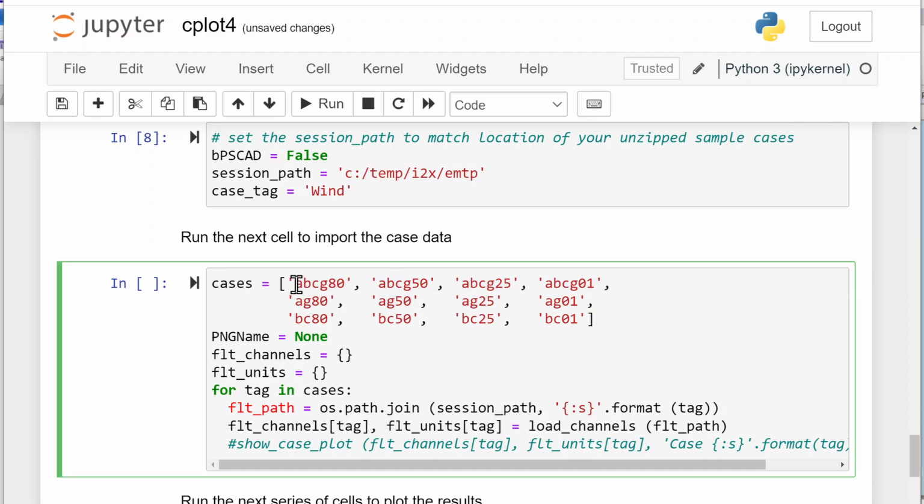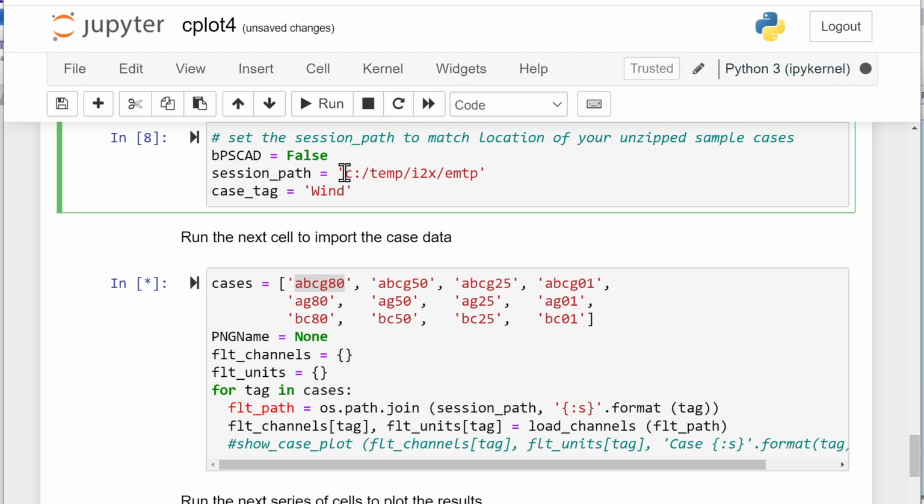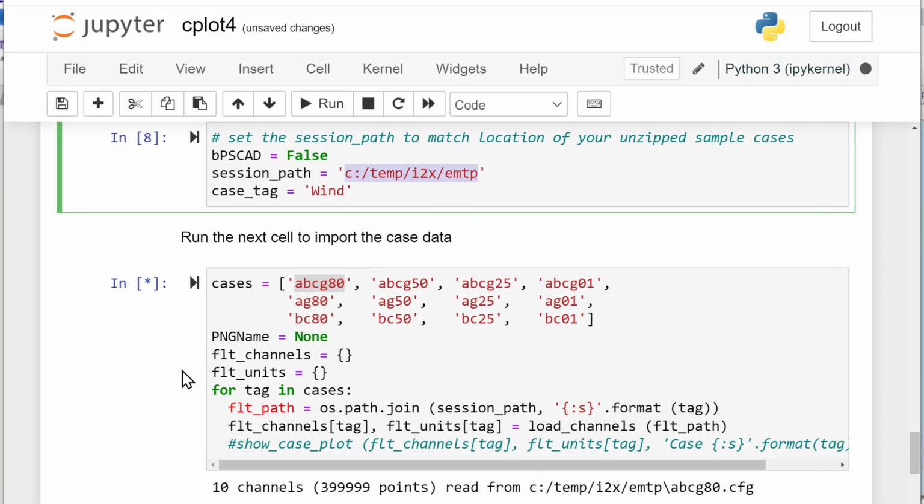And they're using these mnemonics. So in ComTrade, by the way, you're limited to 8 characters in the file name. That's from the old MS-DOS days. So we're not very verbose in these file names and mnemonics. But when I click this, it's going to load all 12 of those ComTrade files, assuming it finds them. And it'll find them if I had the simulations run and put in that output directory.